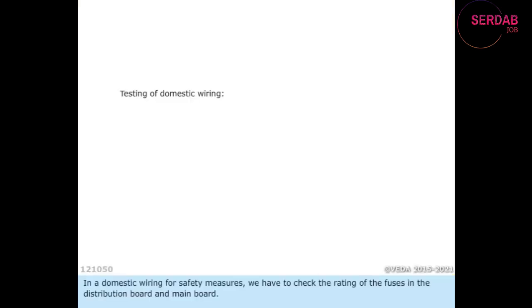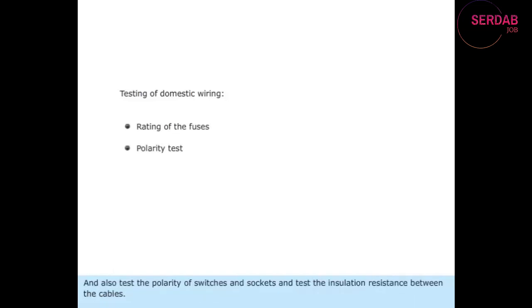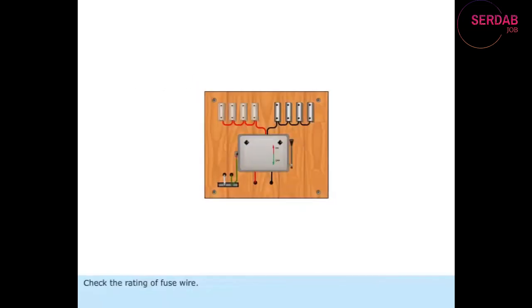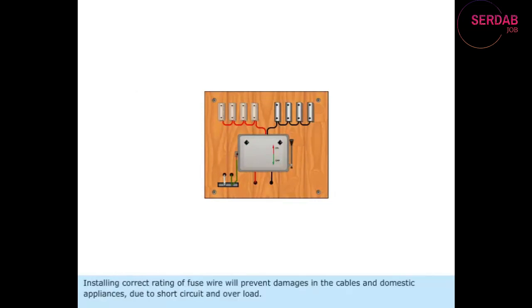In a domestic wiring for safety measures, we have to check the rating of the fuses in the distribution board and main board, and also test the polarity of switches and sockets and test the insulation resistance between the cables. Check the rating of fuse wire. Installing correct rating of fuse wire will prevent damages in the cables and domestic appliances due to short circuit and overload.